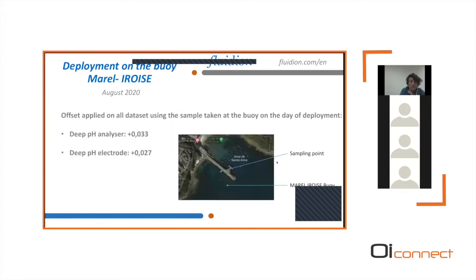During this deployment, here is an aerial picture where you can see where the buoy is, and we took a sample at the buoy during the deployment. This sample was used as a reference to check the calibration, and an offset was applied to correct our dataset to this value obtained from this sample. For the rest of the deployments, we took more samples, but they were taken directly from the jetty, where here you have a monitoring station.